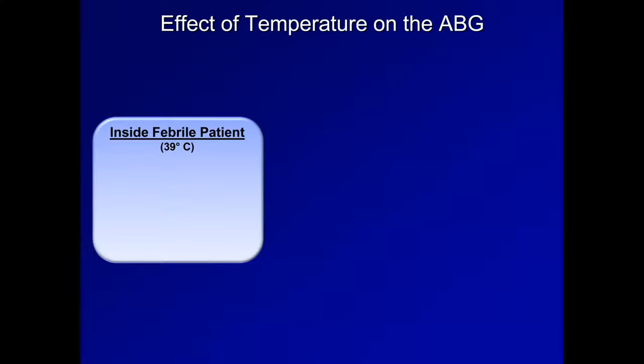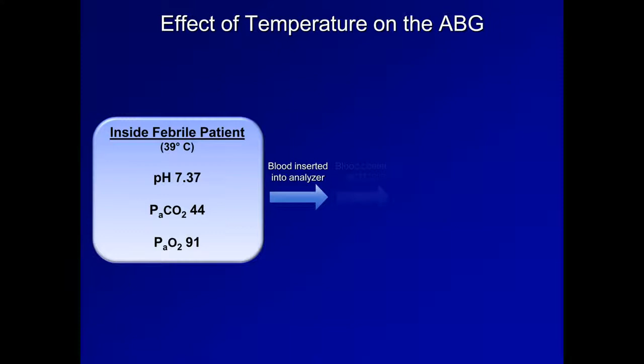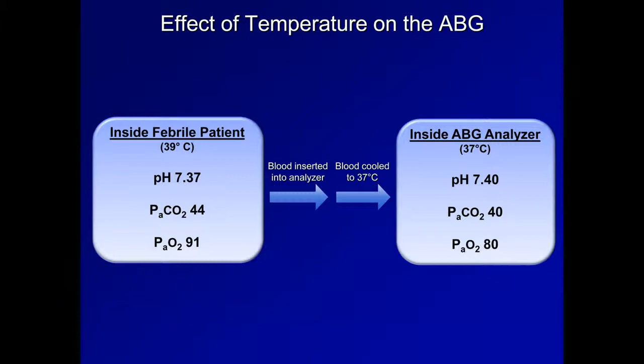For example, imagine a patient febrile to 39 degrees Celsius with a pH of 7.37, PCO2 of 44, and PO2 of 91. If an ABG is drawn, when that blood is inserted into the analyzer, it will be cooled to 37 degrees Celsius. At that point, the equilibrium determining the partial pressure of dissolved gases will slightly shift such that less gas is dissolved in the blood. This will result in lower PCO2 and PO2. In this particular example, the pH of the cool blood inside the analyzer will become 7.40, the PCO2 will be 40, and the PO2 of 80.